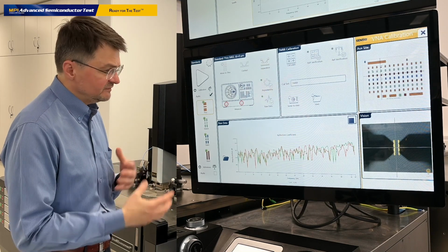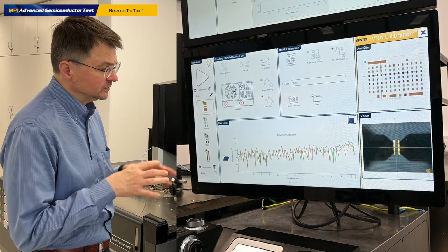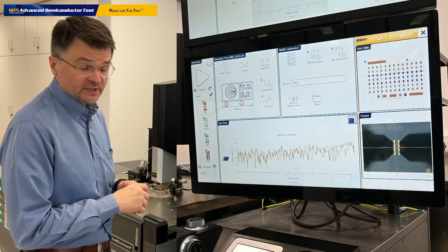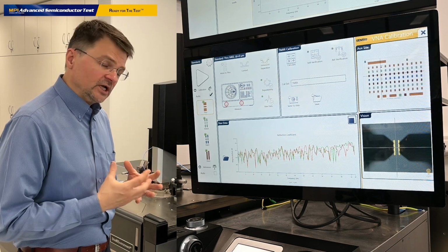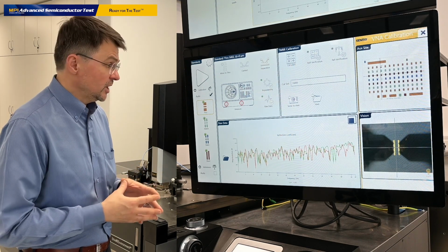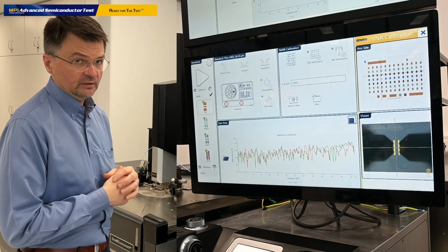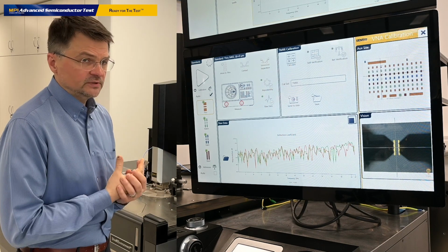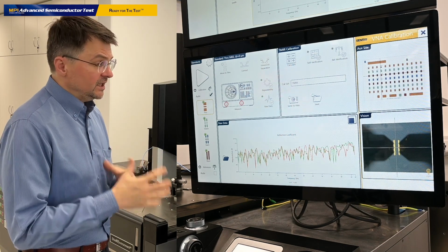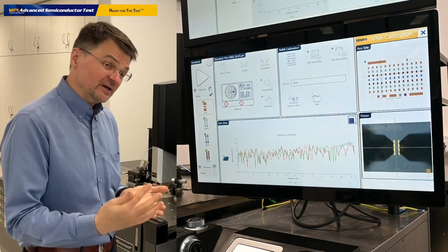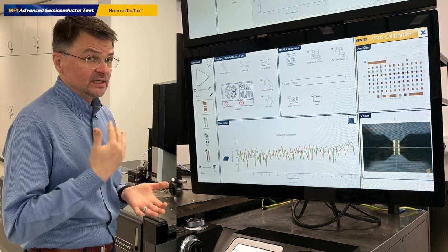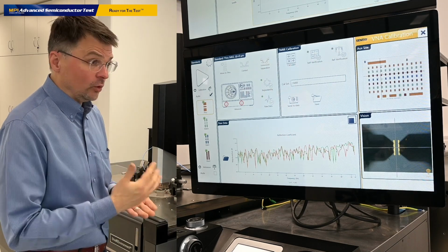Based on this information redundancy, we can already have a look at some very specific characteristics of calibration standards and make a decision if our calibration results are consistent or not. We call it a self-verification algorithm. Even before computing the error terms, Calibria already knows if calibration will be successful or not. We don't need to measure any other reference elements to understand that the calibration will fail or the calibration will be acceptable.